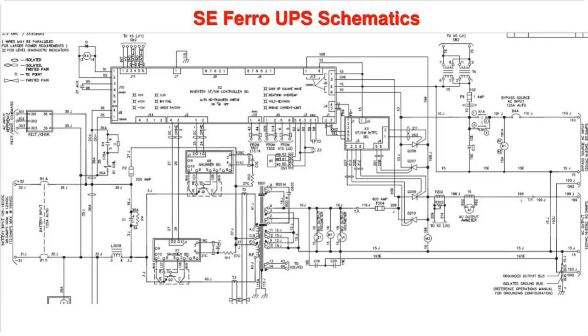And then that goes through this fuse here, which then goes to our inverter bridge. And if you follow this, our positive cable goes in to the center of a transformer. This is a center tapped transformer. Okay. And it's quite simple. We have 2 transistors in our inverter bridge on a small 10 kVA system like this. So if we turn this transistor on, that will allow us to energize this portion of the transformer, because we have to get back to negative through this portion here. So that would give us a negative going portion of the sine wave. And then if we energize this one, we follow the positive all the way through, and that gives us positive with respect to this side of the transformer. That gives us a positive pulse on the second half.